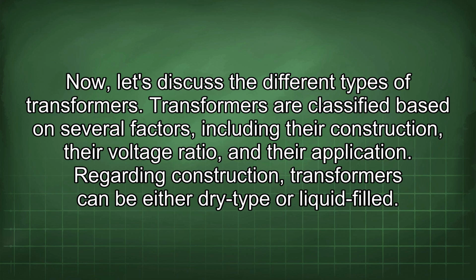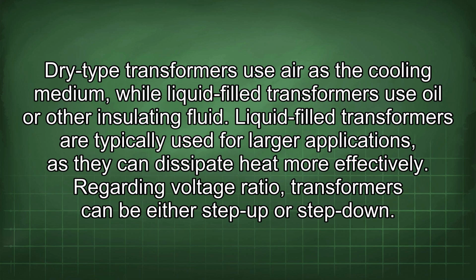Transformers are classified based on several factors, including their construction, their voltage ratio, and their application. Regarding construction, transformers can be either dry-type or liquid-filled. Dry-type transformers use air as the cooling medium, while liquid-filled transformers use oil or other insulating fluid. Liquid-filled transformers are typically used for larger applications, as they can dissipate heat more effectively.